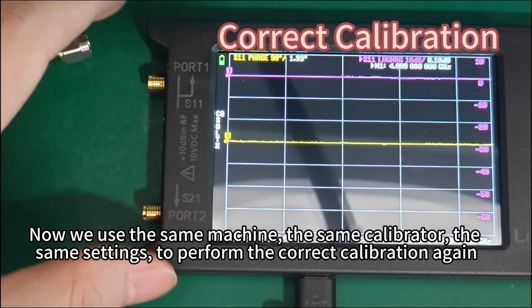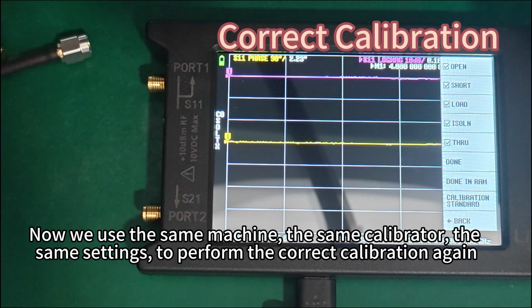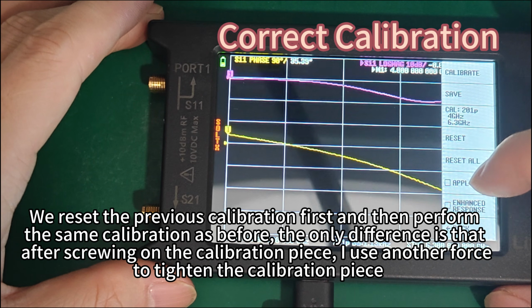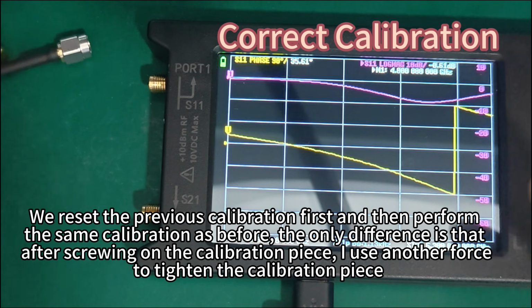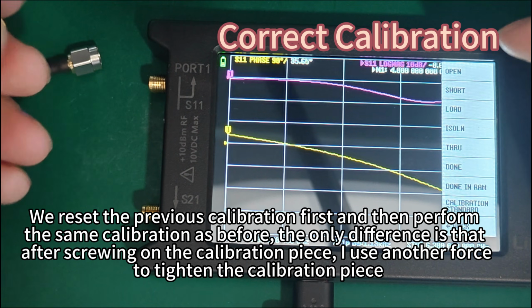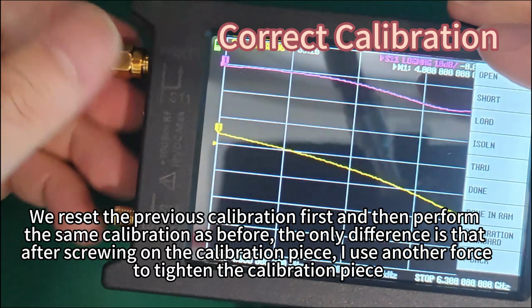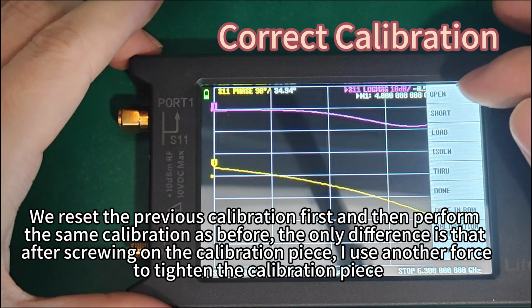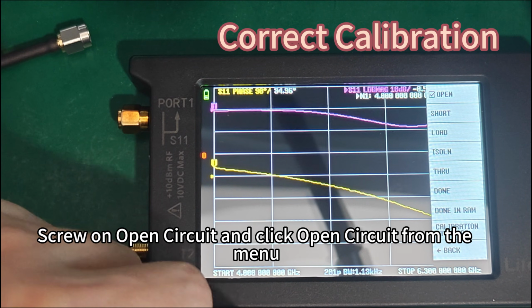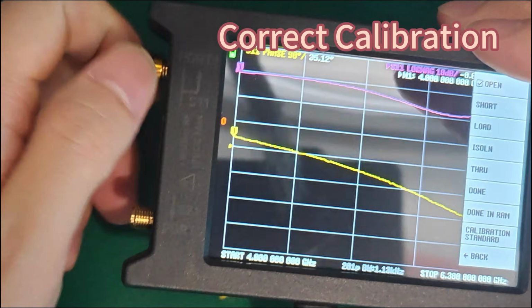Now we use the same machine, the same calibrator, the same settings, to perform the correct calibration again. We reset the previous calibration first and then perform the same calibration as before. The only difference is that after screwing on the calibration piece, I use another force to tighten the calibration piece. Screw on open circuit and click open circuit from the menu.